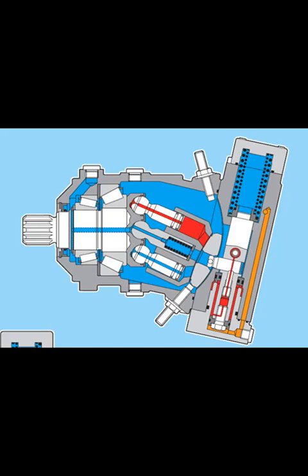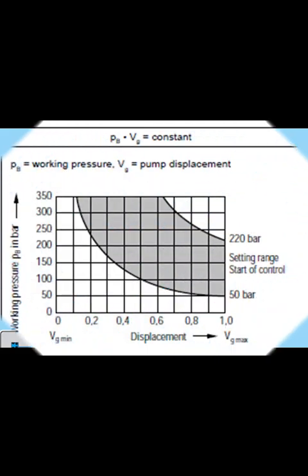In the unoperated, zero-pressure condition, the pump is swiveled to its starting position by means of a control spring. The start of control is adjustable from 50 bar to 220 bar.